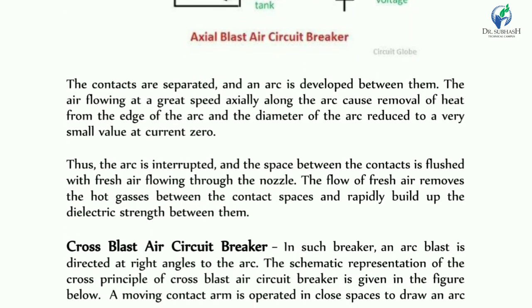The contacts are separated and an arc is developed between them. The air flowing at great speed axially along the arc causes removal of heat from the edge of the arc, and the diameter of the arc is reduced to a very small value at current zero. At current zero, the arc is interrupted and the space in the contact gap is flushed with fresh air through the nozzle, removing the hot gases. This builds up the dielectric strength in the contact space.